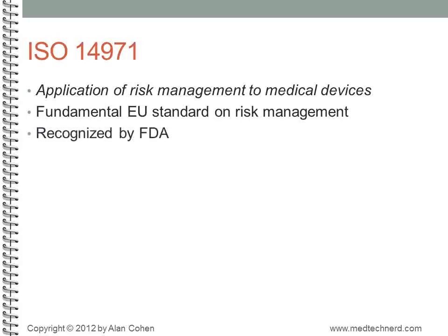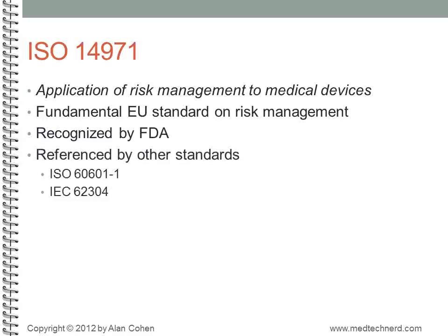The FDA has also formally recognized 14971 as a way to fulfill its own requirements around risk management, so most device makers choose to conform to this standard in order to meet both EU and US requirements. 14971 is also referenced by a number of other standards, such as ISO 60601-1 and IEC 62304, which are themselves basic safety standards that we'll discuss more in future videos. Standards referencing other standards is not unusual.